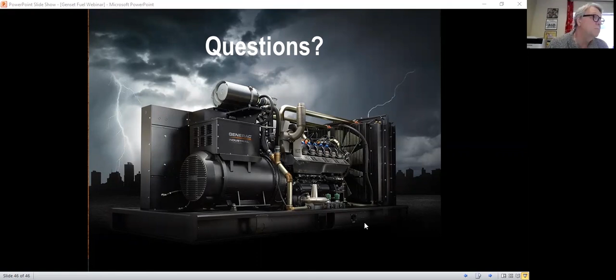Good question. A dual fuel generator is almost free—not quite, but we just have a natural gas line coming into the generator and a propane line, with a little device with a spring. When natural gas pressure is available, it pushes a piston over and uses natural gas; if the natural gas pressure ever fails, the spring pushes it the other direction and it uses propane. For a dual fuel generator, I'm guessing on a smaller generator you'd pay maybe another $400—it's a very small price difference, and labor is the same. You just have to run a natural gas pipe and a propane pipe there, but that's it.